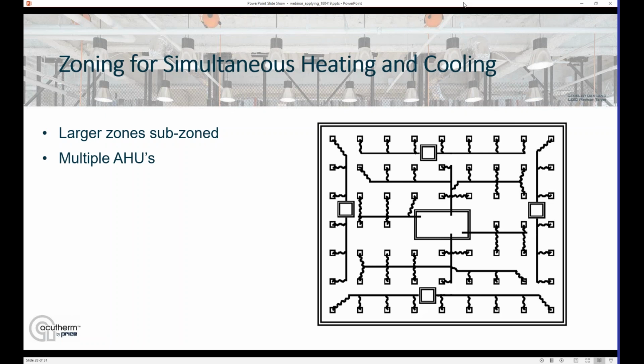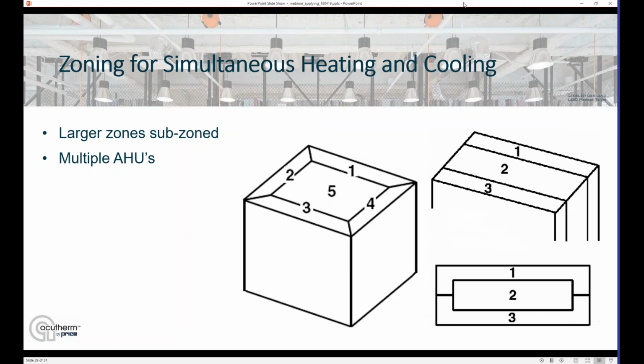A great method to work with that's a very energy efficient method is multiple air handling units. This way there's no reheat. If we put on an air handling unit to cover the north perimeter, an air handling unit to cover the south perimeter, same for the east and west, and then a fifth on the interior, that means each area of the building has its own air handler, and if the north needs heating while the south needs cooling, you're not bringing any reheat on, you're just switching that unit over to the different mode. So that can be a very energy efficient approach.